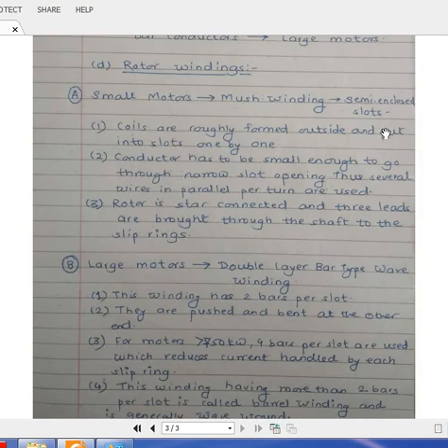When semi-enclosed slots are there, your windings are roughly wound outside and they are put slot by slot inside. Because you have to control your area of conductors, you have to increase your current based on current density calculation. And because your current is going to increase, you have to apply a number of parallel paths. So several wires in parallel per turn are used. The rotor is star connected and three leads are brought through the shaft to the slip rings.